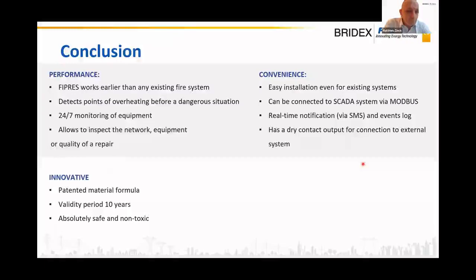Finally, the performance of the FIPRES system relies on the fact that it works earlier than existing fire systems. It detects overheating points. It's basically continuous. It works 24/7. It allows you to inspect each part of your equipment that you believe could be sensitive. It's easy to install. It can be connected to the SCADA or your BMS system, and it also has a dry contact output to connect to an external alarm system. So we believe it's the right solution for fire prevention inside electrical switchgear and panels.